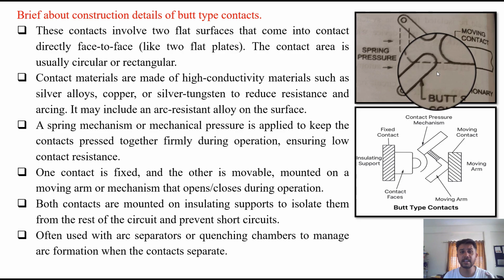Contact materials are made of high conductivity materials such as metals or metal alloys, so that the contact resistance and arcing may be reduced. These materials are silver alloys, copper, or silver tungsten, that is a mix of metals, so it forms an alloy. It may include an arc resistant alloy on the surface. These may reduce the contact resistance and arcing. A spring mechanism or mechanical pressure is applied to keep the contacts pressed together firmly during operation, ensuring low contact resistance and smooth passing of current during normal operating conditions.